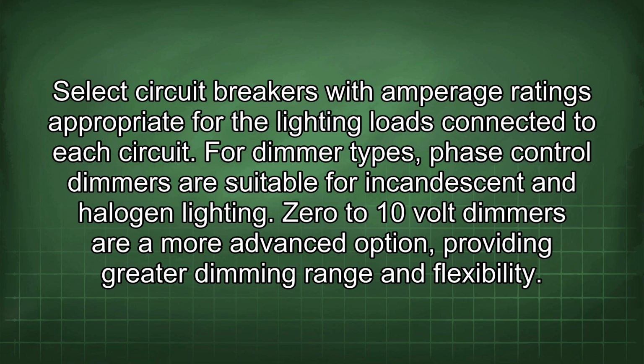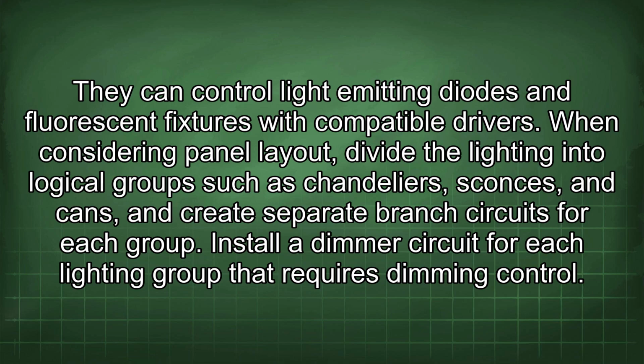For dimmer types, phase-controlled dimmers are suitable for incandescent and halogen lighting. 0 to 10 volt dimmers are a more advanced option, providing greater dimming range and flexibility. They can control light-emitting diodes and fluorescent fixtures with compatible drivers.